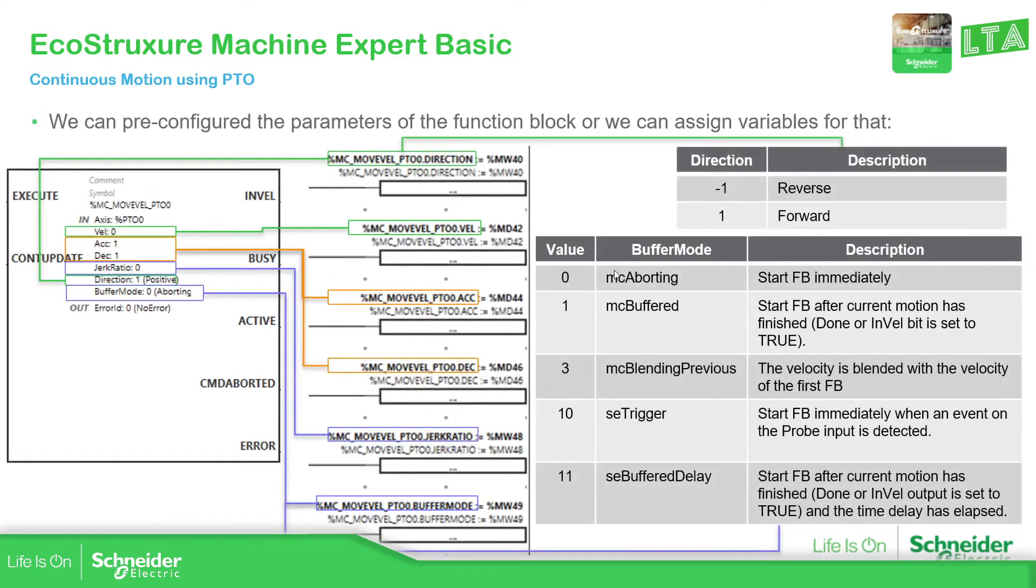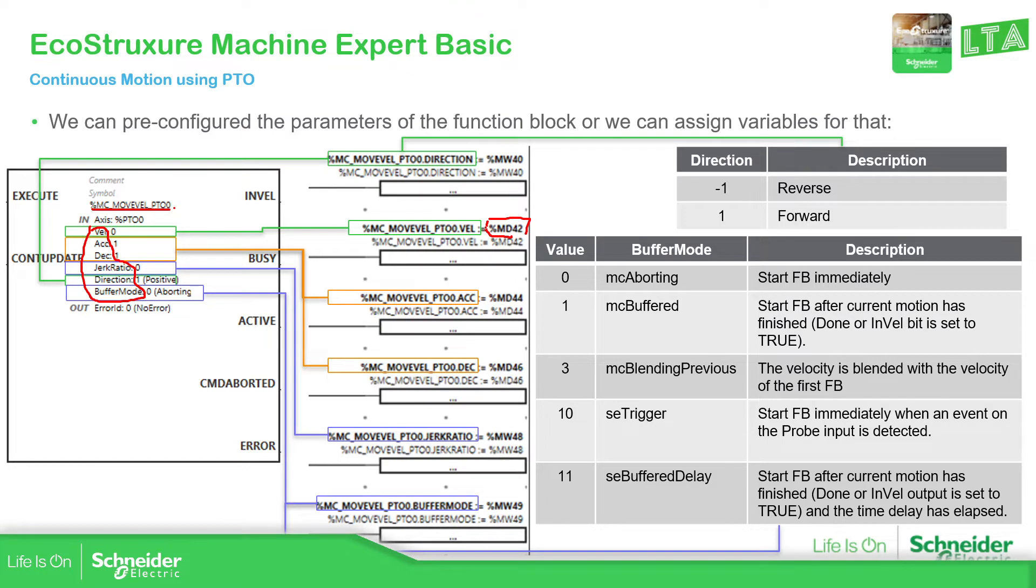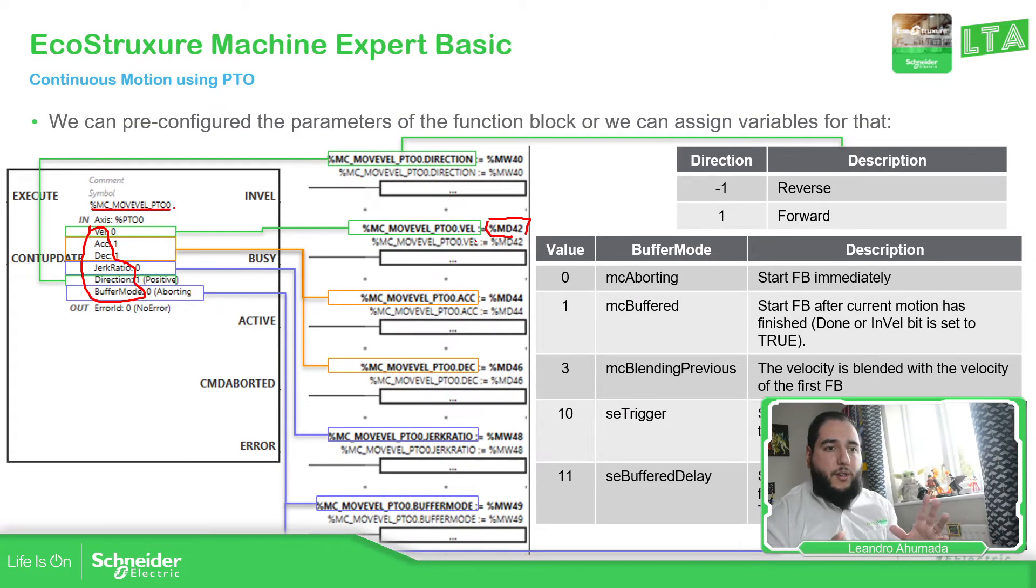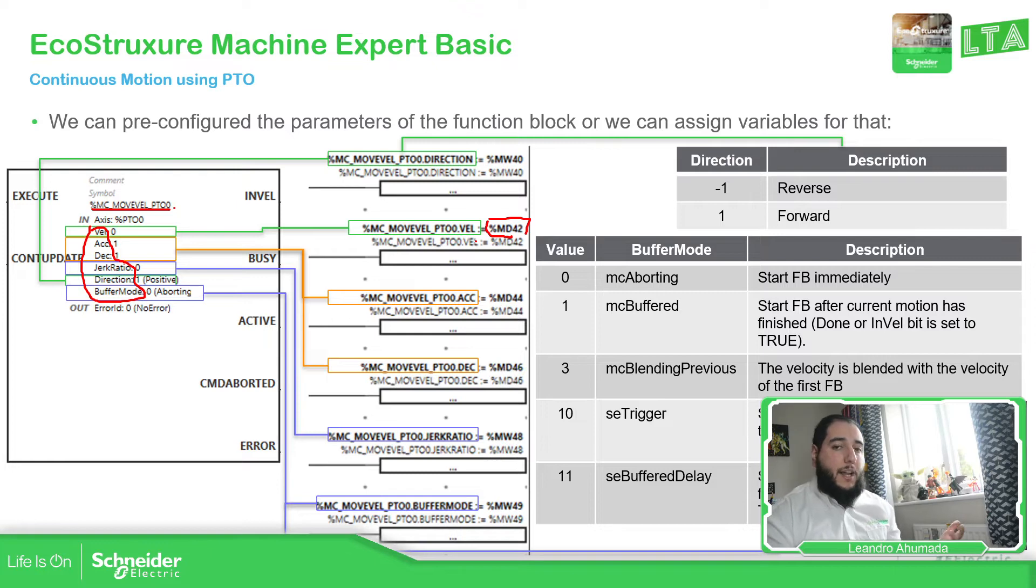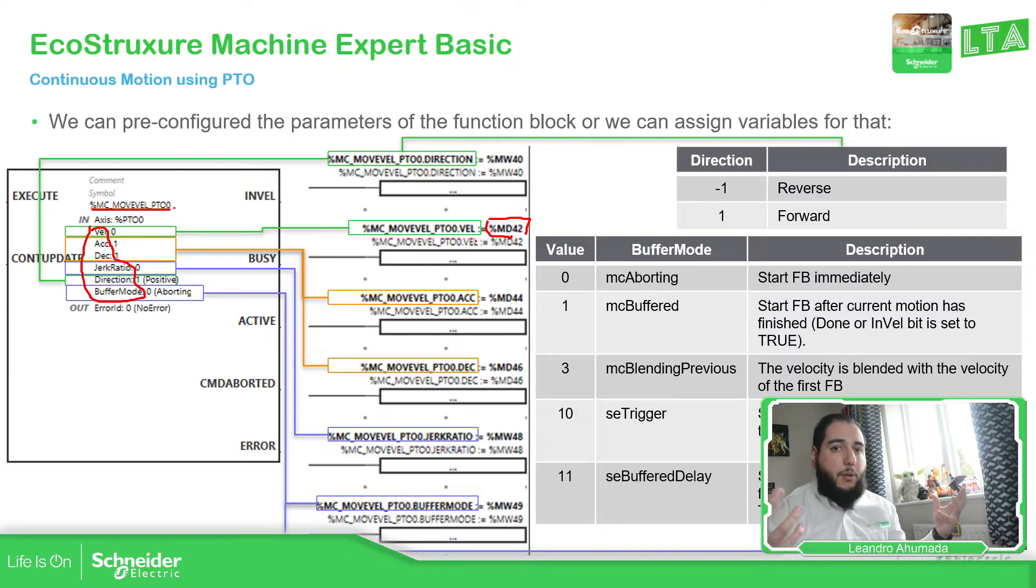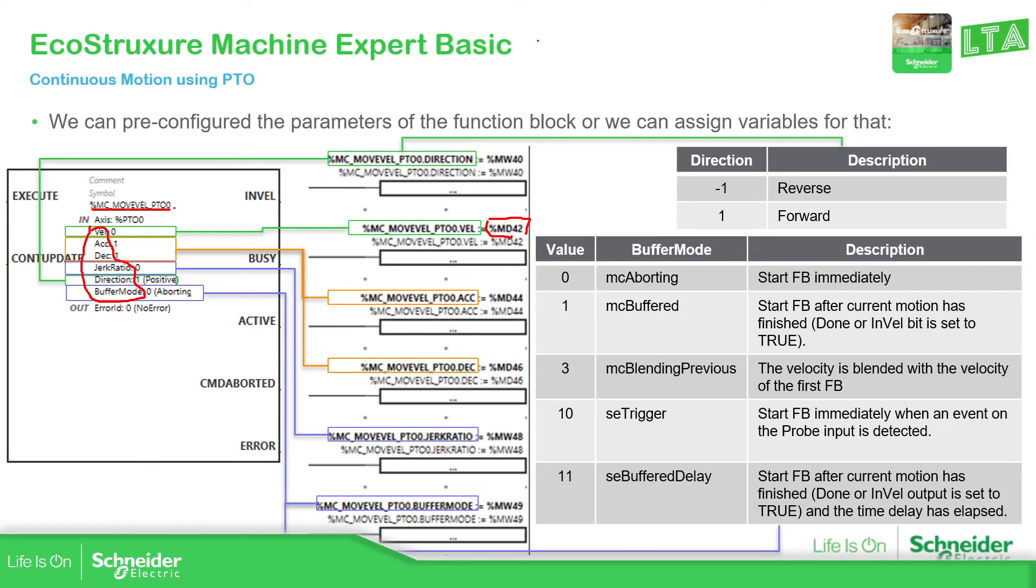So you can use the pre-configure for that, but another solution would be to use the name of the instance dot the name of these variables that we have over here to access to this information remotely. For example, in this case, if I want to change the velocity using an HMI, you just need to use the %MD and then assign the value to the velocity. I have already created different videos how you can communicate with the HMI. So if you're using Vijeo Designer or Operator Terminal Expert, you just need to import the project and see all the variables and then just use your imagination to create the HMI. So let's continue with this.